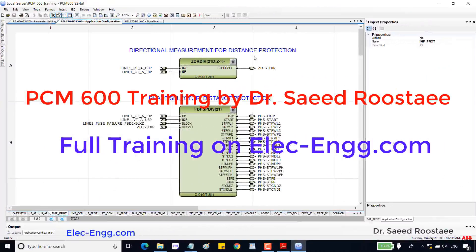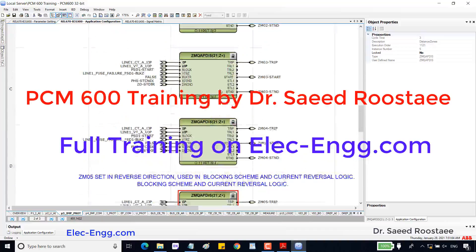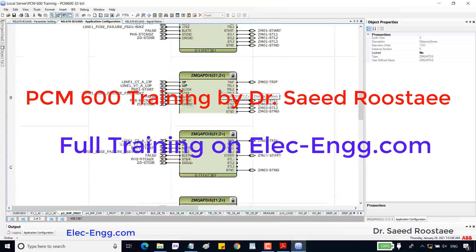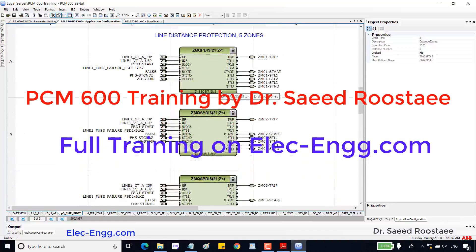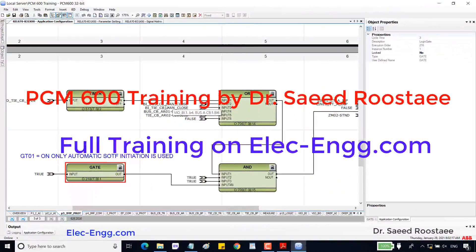This directional block requires voltage and current signals to calculate fault directions. Zone 5 is set to the reverse direction. We should check our project and diagrams, and if needed, set other zones to the reverse direction as well. We can set the parameters accordingly and check the manual.